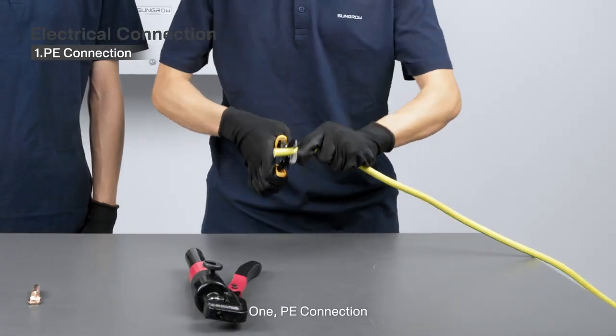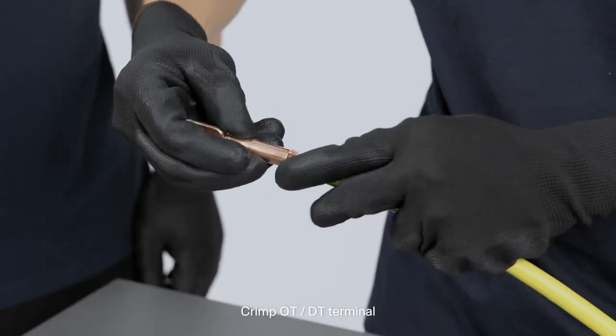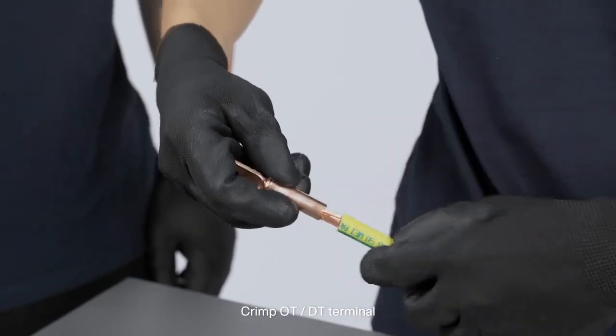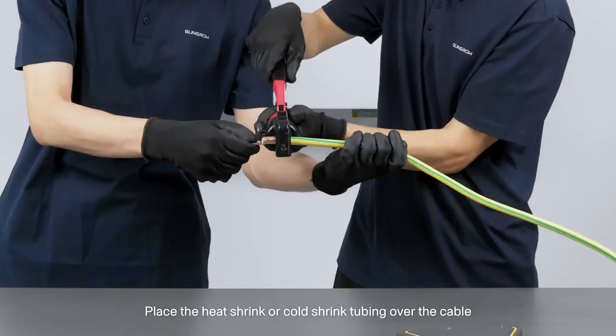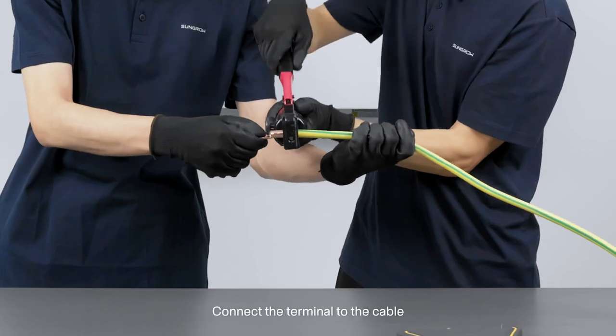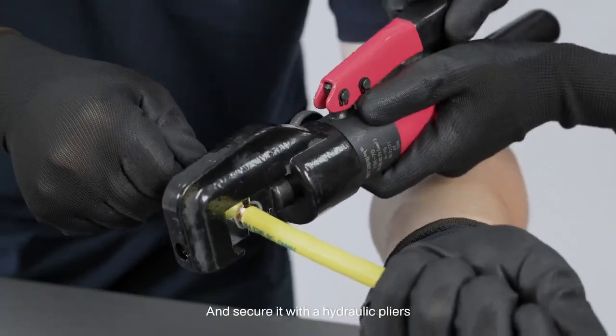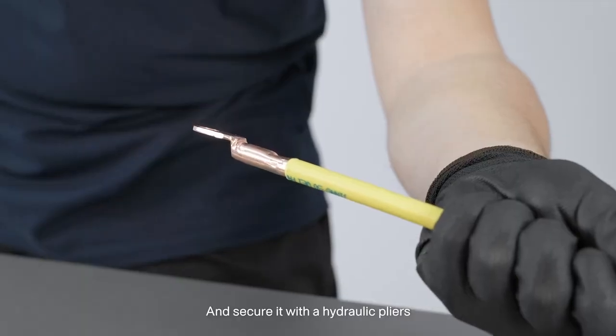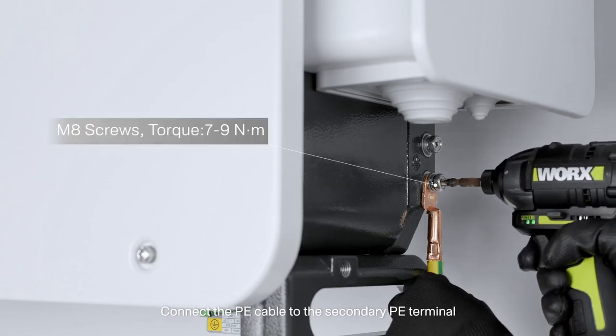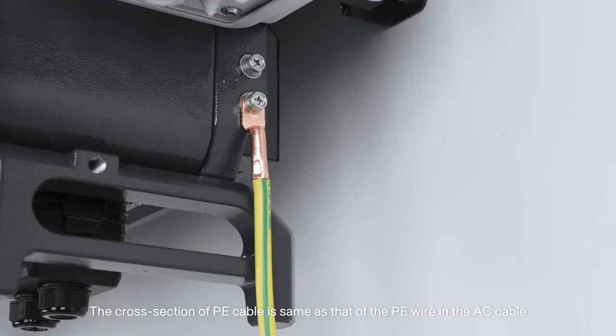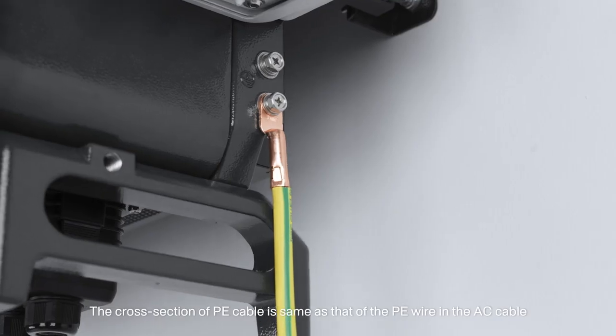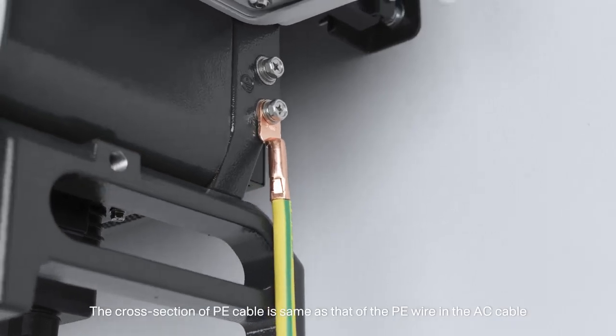1. PE connection. Crimp OT or DT terminal. Place the heat shrink or cold shrink tubing over the cable. Connect the terminal to the cable and secure it with the hydraulic pliers. Connect the PE cable to the secondary PE terminal. The cross-section of PE cable is same as that of the PE wire in the AC cable.